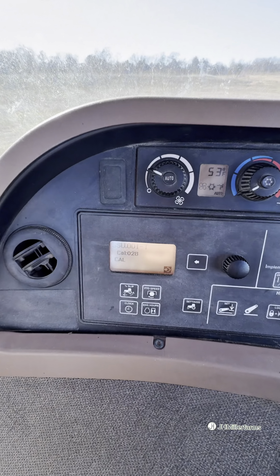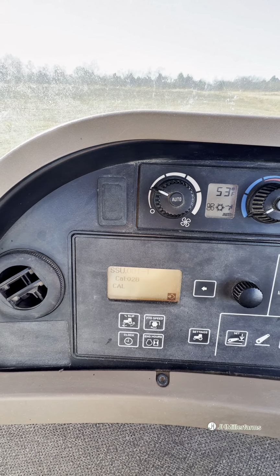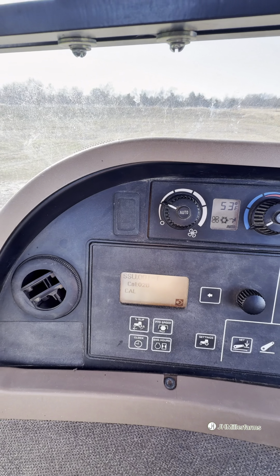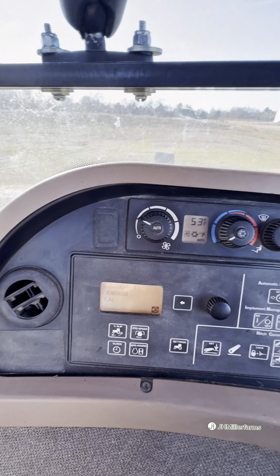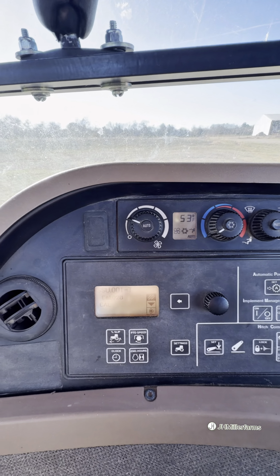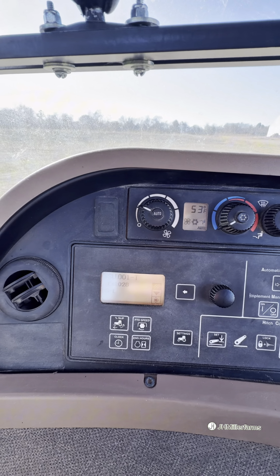Since we changed the valve, we have to calibrate it. It is SSU 28 for the calibration. You have to be in tech mode to access 28. We're going to go ahead and hit the accept button there.